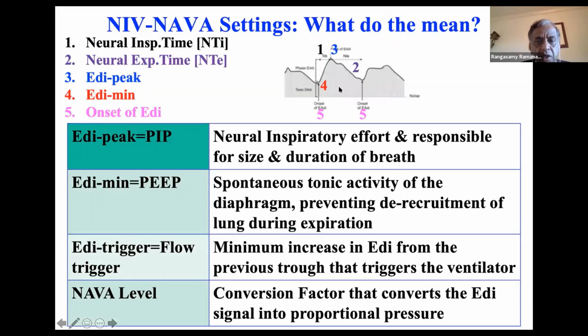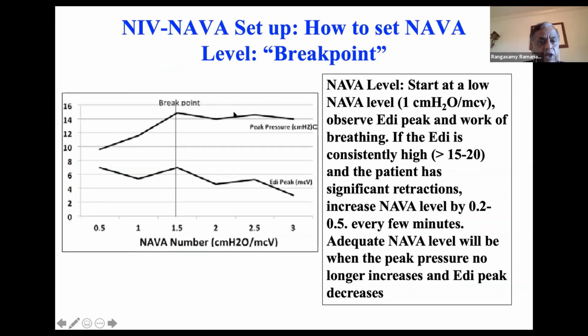This is all background noise, okay? That's why you want to keep your Edi trigger around 0.5. If you set it at 0.3, you're going to have a lot of auto-triggering. The machine thinks the baby is taking a breath. It's very sensitive. We already talked about the break point, so I'm going to skip that. Generally, you start the NAVA level at 1 centimeter of water.